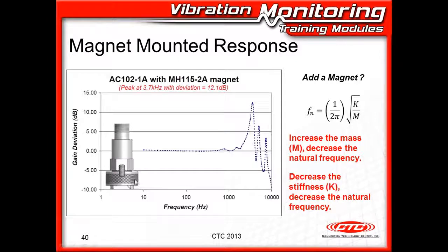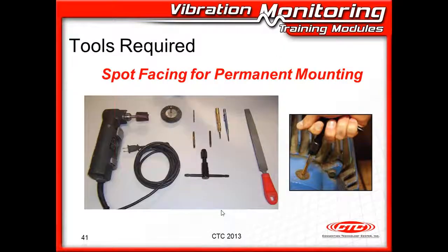Don't be fooled either. It's not the size of the magnet that matters. The different sizes or pull strengths are simply to keep the magnet attached to the machine. So a larger magnet has a larger mass, a smaller magnet has a smaller mass, but they all do about 2,000 hertz. That's on a 2-bar curved surface magnet. Remember, if you want to go with a magnet and a portable data acquisition system, you really want a flat magnet with a mounting target. It'll perform much better, especially for those doing peak view. That's the way to go.